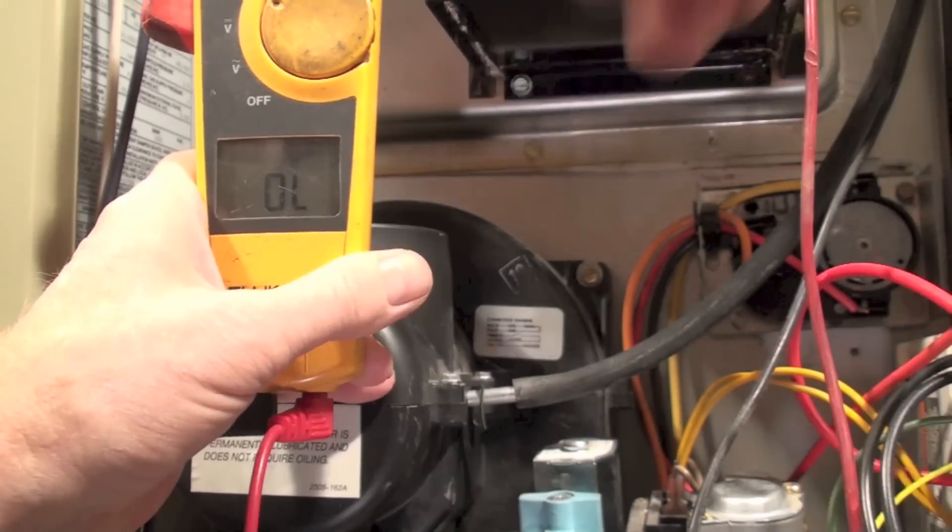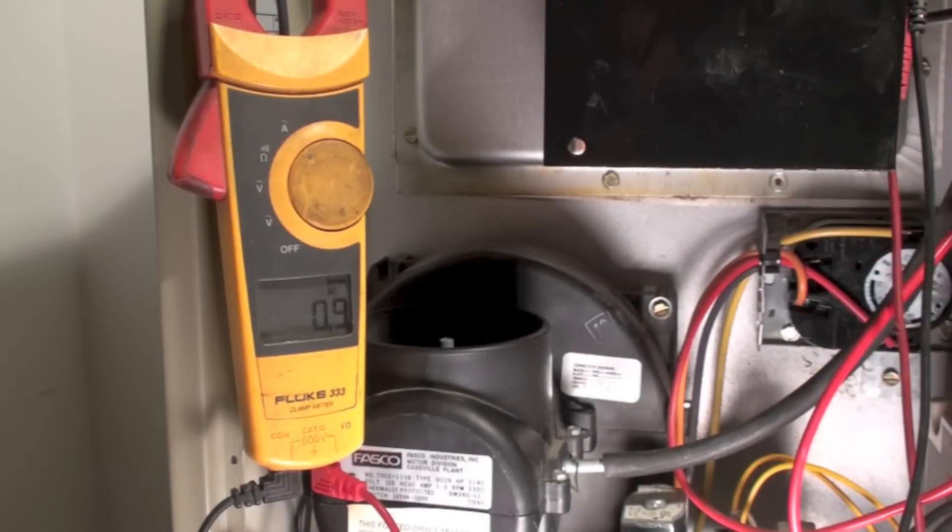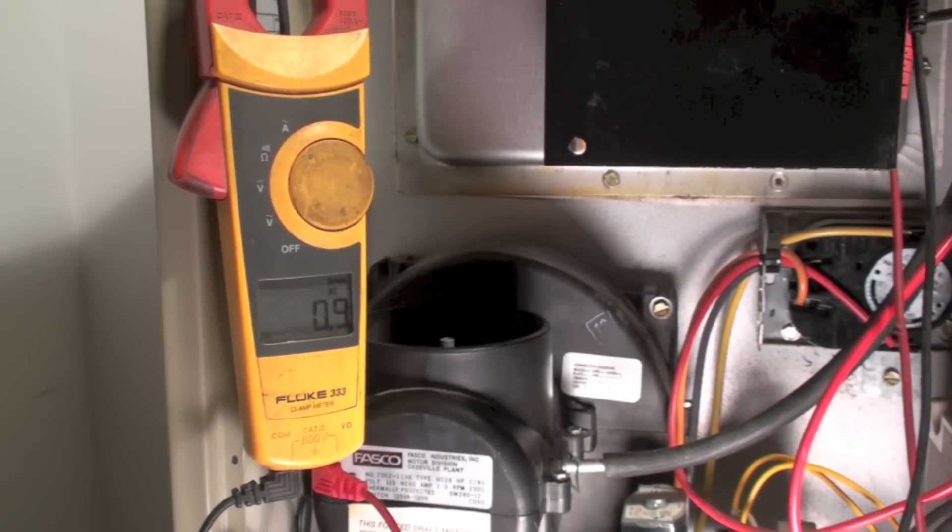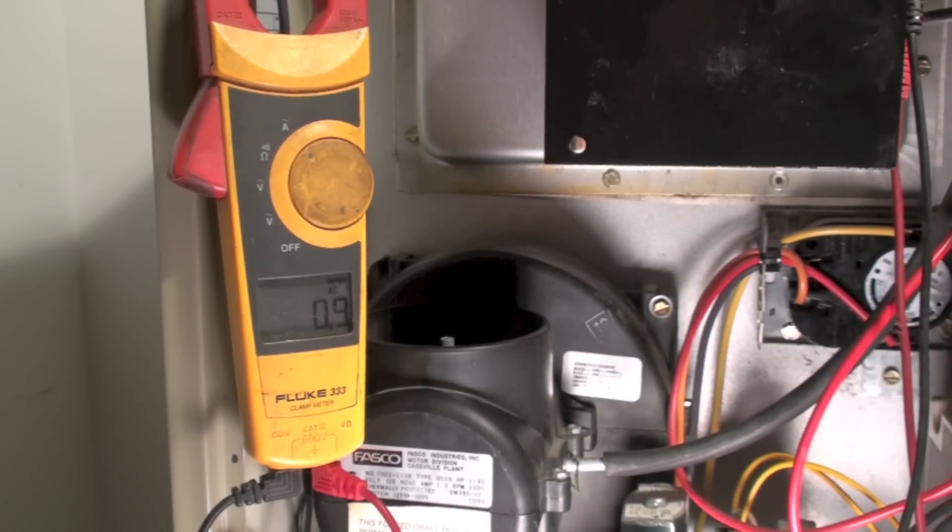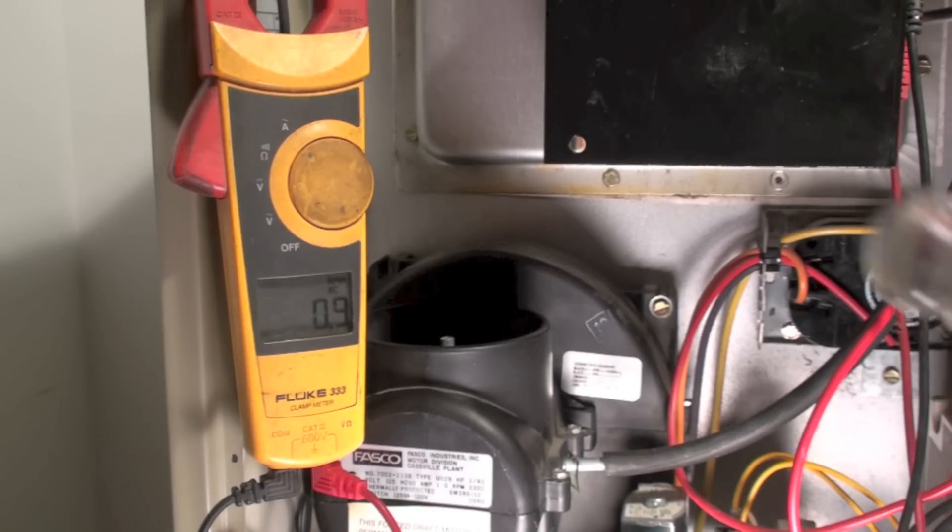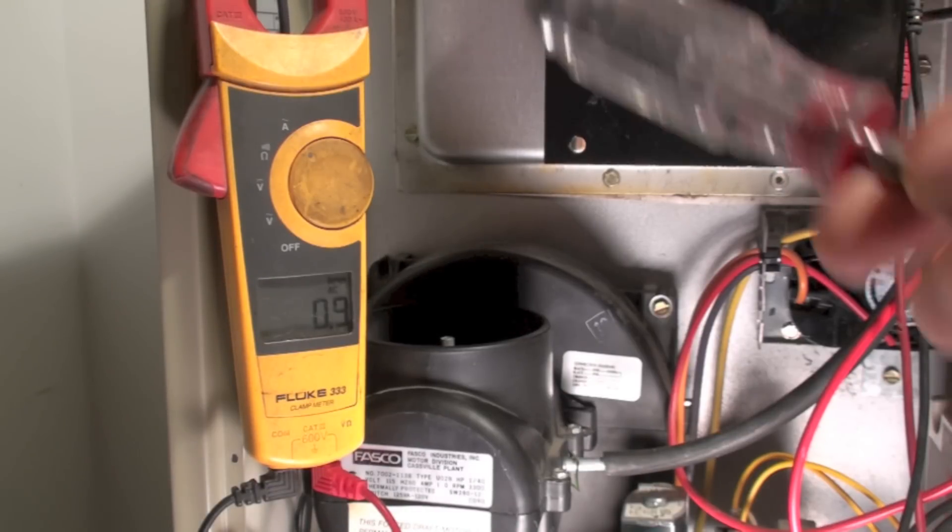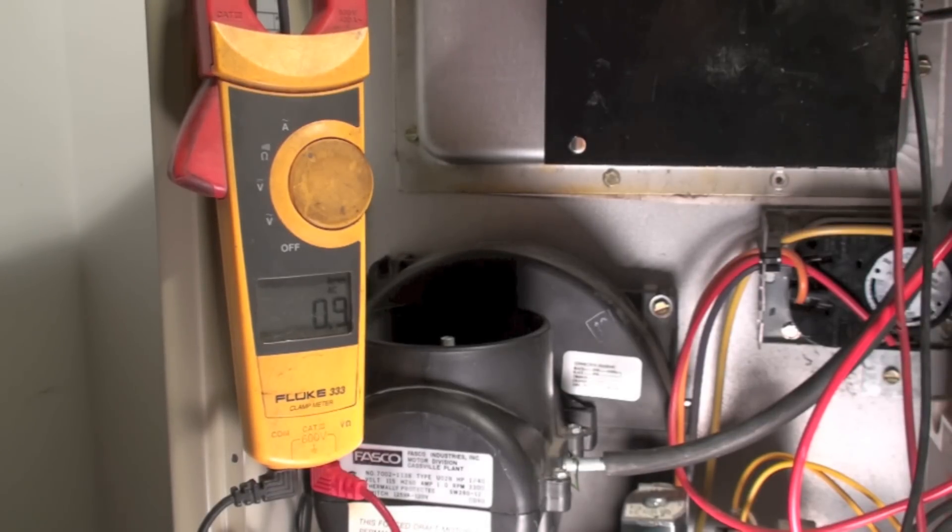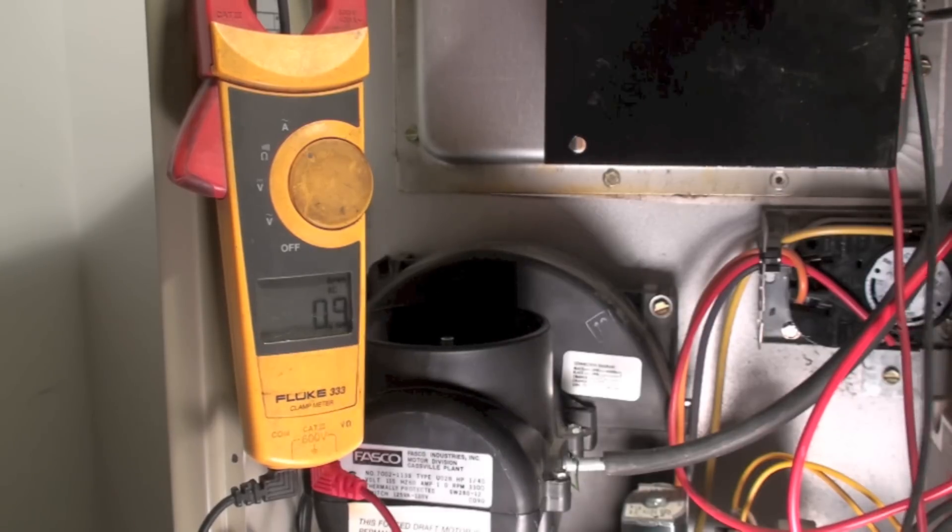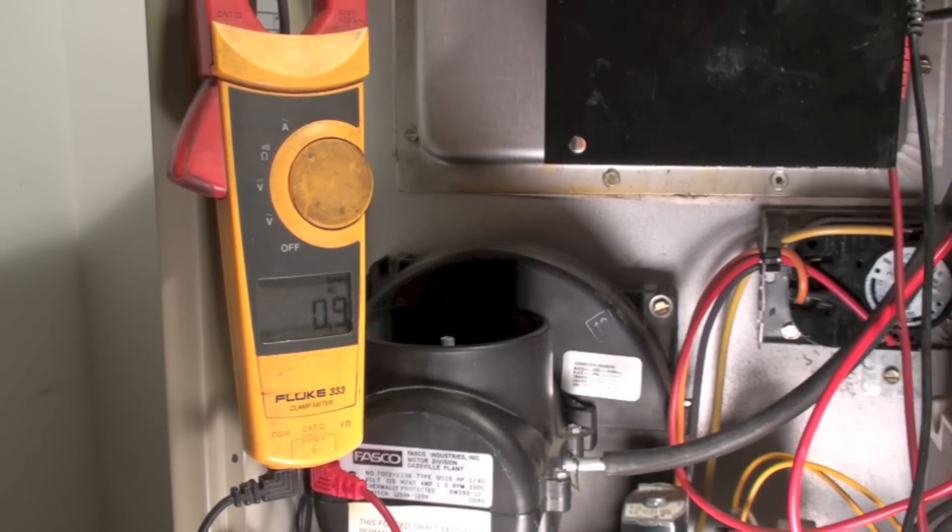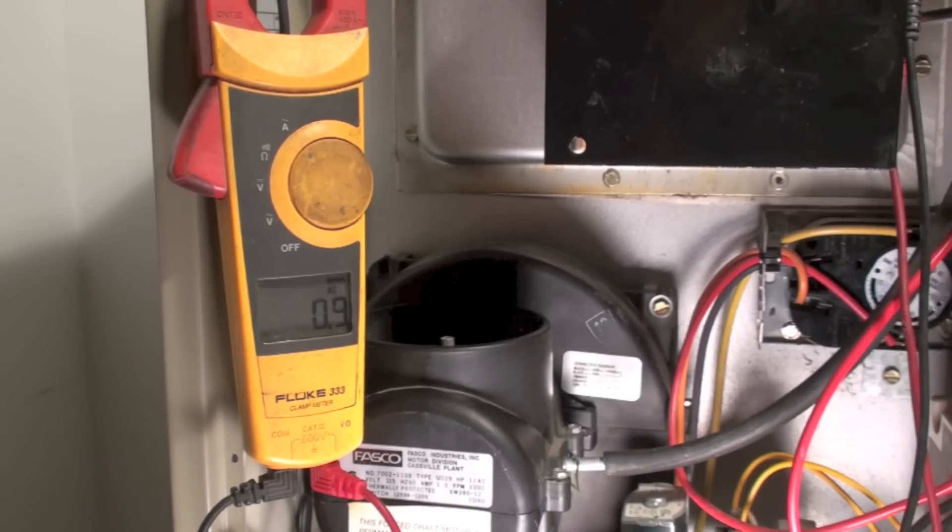So that's the pressure switch in the GUA model furnace. The pressure switch has no way to test itself, it does not have to move, it does not have to prove either open or closed before the burner will start. So it's very common for these things to eventually stick. And when they stick, of course they don't work and there's no protection for it.